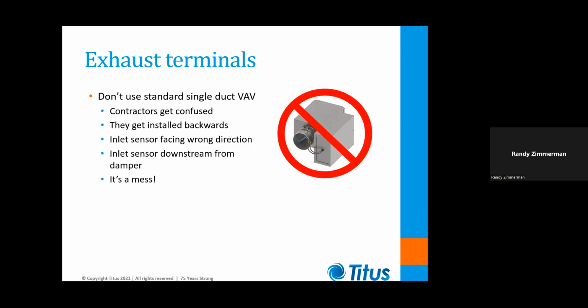Now, I often get calls on these afterwards where people say, gee, how do I fix that? We just installed 50 of these backwards. And of course, they've got no room to redo the ductwork. The usual solution is to remove the sensor, flip it around the right way, and put it further downstream in the ductwork to get it away from the influence of the damper. Likewise, you can also get a retrofit sensor assembly from us and mount that further downstream in the ductwork. But just to avoid all those problems, it's better just to get the proper box.